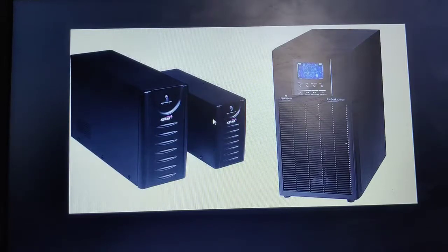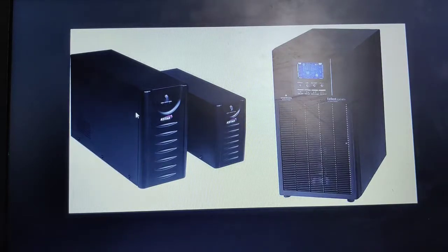By the time, it will be monitoring, and if it gets to know that the power supply is off, that there is a failure of the current, automatically it will switch to the offline UPS, and then power supply will start being provided from the offline UPS to the computer system, so that the user has time to save the data and can work for a few minutes to a few hours, depending upon the capacity of the UPS. The switch over to the battery, however, can require at least several milliseconds, during which time the computer is not receiving any kind of power.